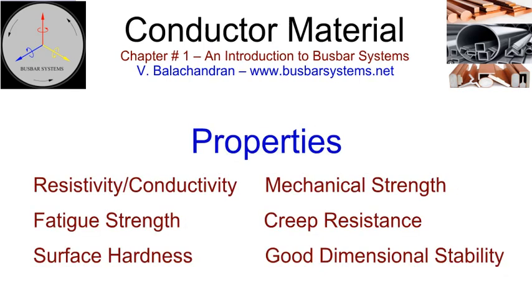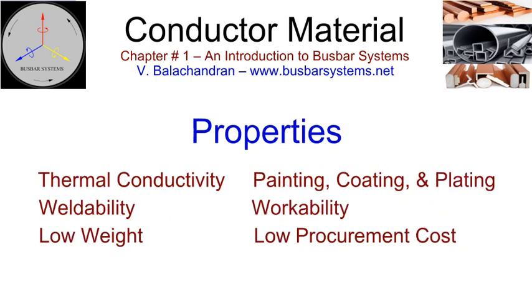The selection of conductor material is dependent upon application, ambient environment, and system parameters, among other project-specific requirements. Some of the properties that need to be considered before selecting the material are resistivity, conductivity, mechanical strength, fatigue strength, creep resistance, surface hardness, good dimensional stability, thermal conductivity, painting, coating, and plating, weldability, workability, low weight, and low procurement cost.